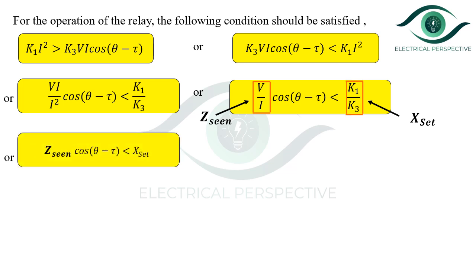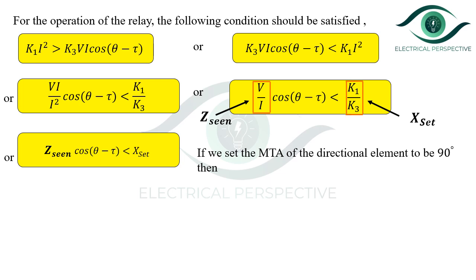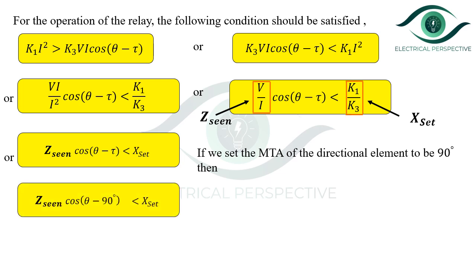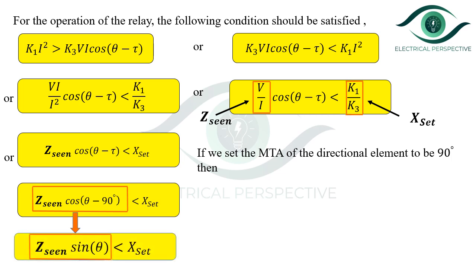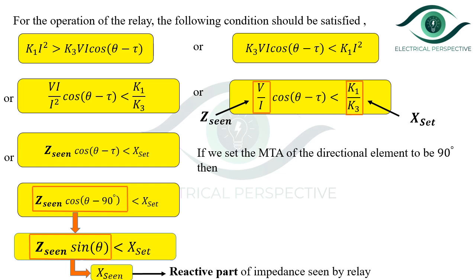So we get Z_seen·cos(θ − τ) < X_s. If we set the MTA (maximum torque angle) of the directional element to 90°, then Z_seen·cos(θ − 90°) < X_s. Replacing τ with 90°, Z_seen·cos(θ − 90°) = Z_seen·sin(θ), which should be less than X_s. Z_seen·sin(θ) is the X_seen — the reactive part of the impedance seen by the relay. So the trip law is: X_seen < X_s.